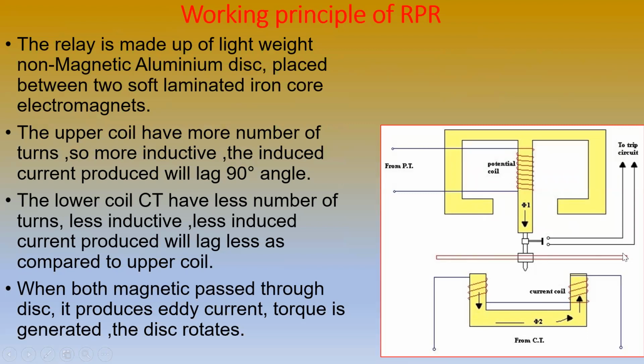So this is called the aluminum disc. This is a lightweight non-magnetic disc which is placed in between the soft laminated iron core electromagnets. So at the top we have one iron core magnet, and down below we have another iron core magnet. In between we have this aluminum disc. The upper coil has more turns, so the induced current which is produced will be more inductive, and it will lag by 90 degrees. So there will be a positive lag of 90 degrees.